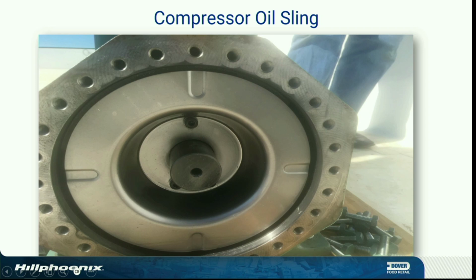And those journals, has anybody seen the inside of a CO2 compressor? On a regular standard crank, your journals are about this big. On a CO2, they're three times the size. They've got Teflon with a special coating put on it. They're very hardy.